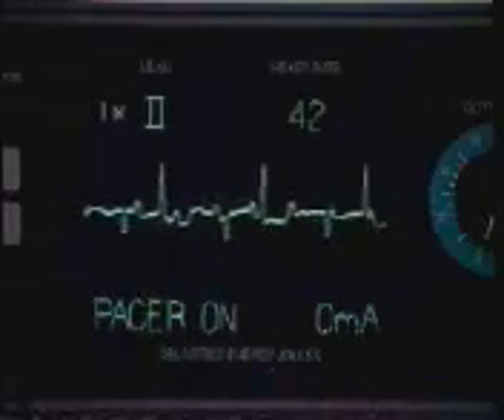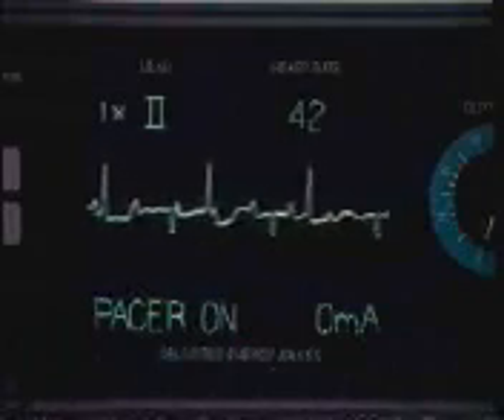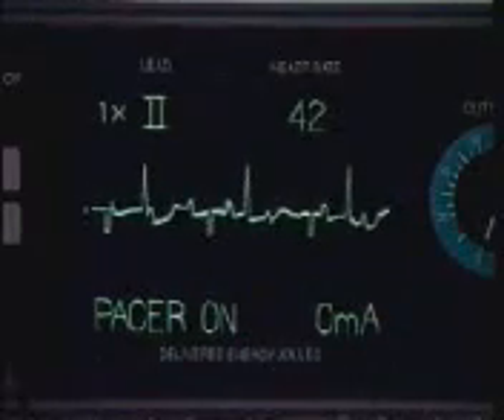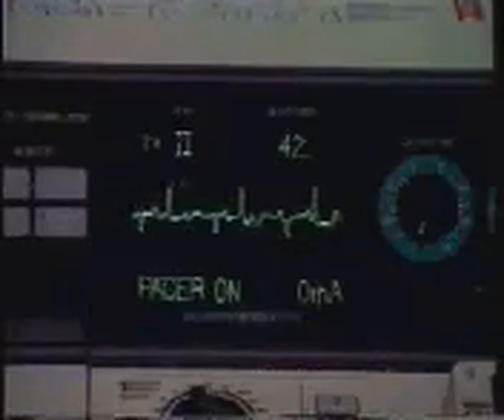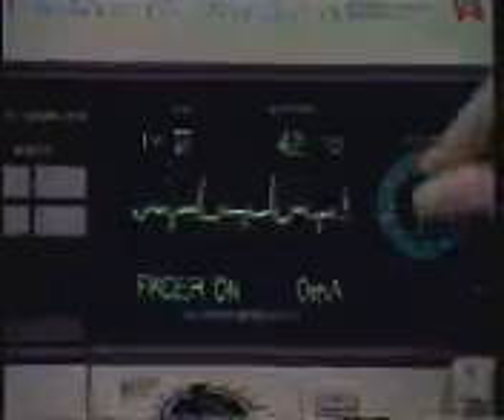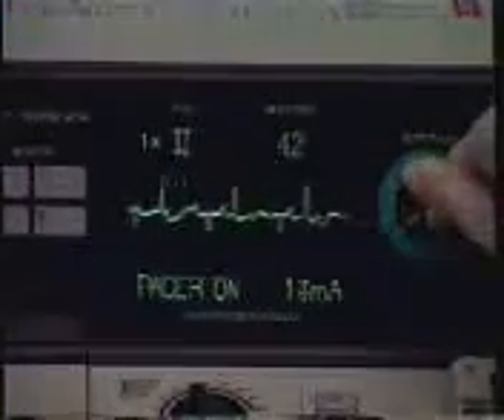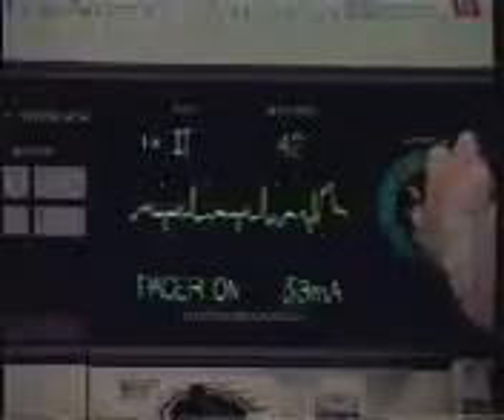Observe the pacing artifact, a wide downward deflected marker, and verify that it falls in diastole if the patient has a heart rate. Average pacing thresholds are 55 to 65 mA. Increase output mA slowly until stimulation is effective, at which point the intrinsic QRS complexes will be suppressed.